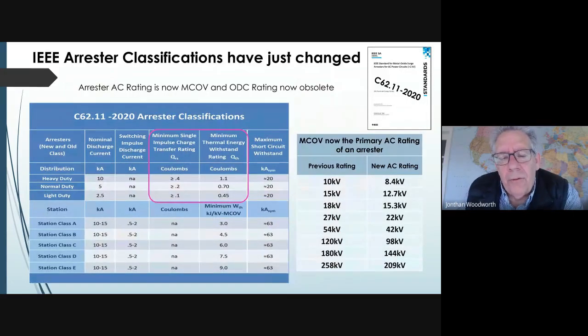Every arrestor has a classification, whether it's classified by IEEE standards or IEC standards. Every arrestor manufactured today has to be tested to some minimum levels. Most of the time, a country will adopt the international standards, but oftentimes they make them a little bit tougher. For instance, I'm not sure what the India standards are, but India has its own set of standards for surge arrestors, but they're oftentimes very much in line with the IEC standards.